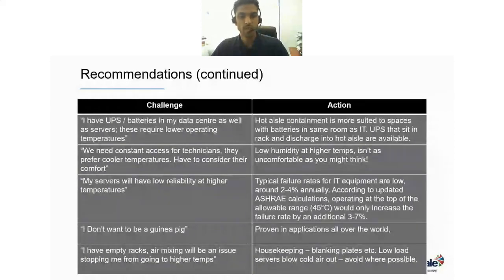Next is I don't want to be a guinea pig. This is, of course, not a new technology. This is proven all over the world. All the hyperscalers are doing this, so it's not new. I have empty racks. Air mixing will be an issue, stopping me from going to high temperatures. So again, it's housekeeping stuff, such as blanking plates in place, etc. Low load servers blow cold air out, so that needs to be avoided.